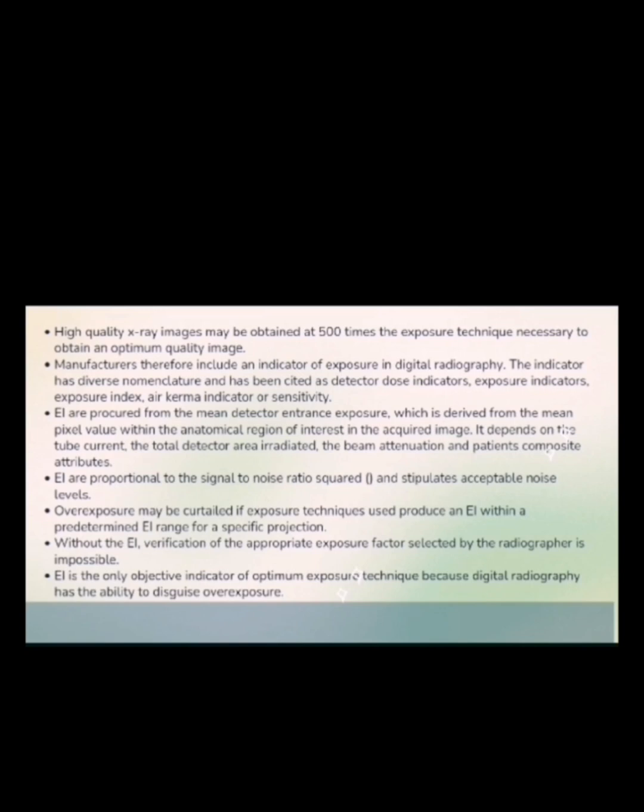And next is, without the exposure indicator, verification of the appropriate exposure factor selected by the radiographer is impossible. That's because the predetermined range will be recommended by the equipment manufacturer. However, the range may be further tailored by the radiology department according to their image quality needs for specific projections.